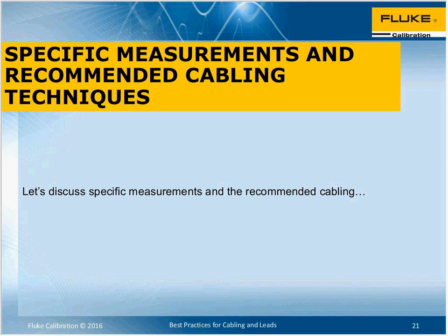So one of the things we've always done when we've been setting up our labs is we've looked for these kinds of things before we start any serious measurements with a new setup, is to go in there and, as I hinted, take one of your most sensitive measurements, and just turn on and off these systems and see if you can detect an effect. So, have the system shut down, set your measurement up, say 10 volts or 1 millivolt out of your AC calibrator at a set frequency, and then turn the fan on and see if the reading changes. Does it glitch when you hit the button to turn the fan on? Does it stay changed? Those kinds of things are the sort of techniques.